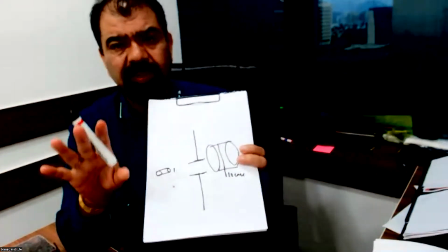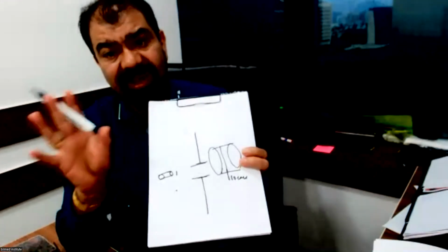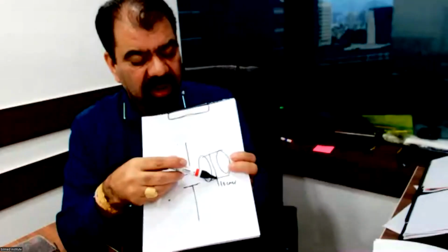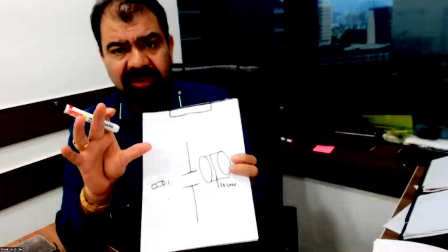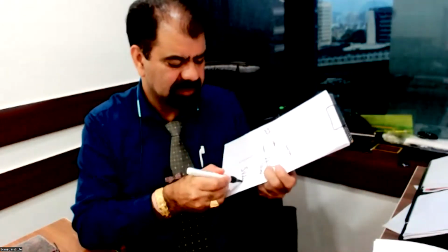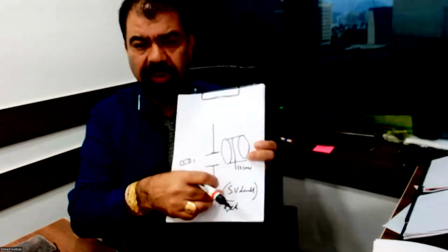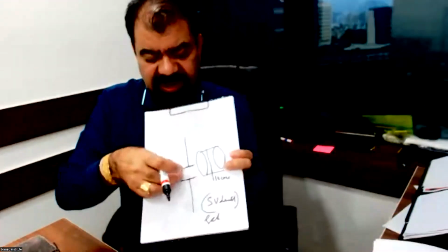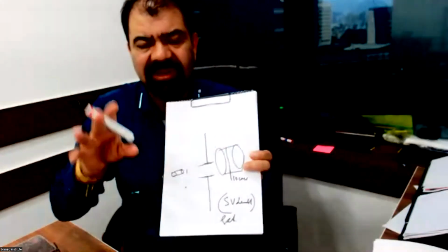This gate has to be about 70% of the vessel. Sometimes I have to increase it, sometimes decrease. For that, I have an option which is SV length or gate width. When you press or rotate this, you will see that the gate width will increase or decrease. So SV length is the gate width in GE machines.